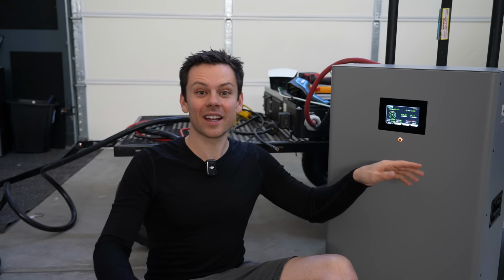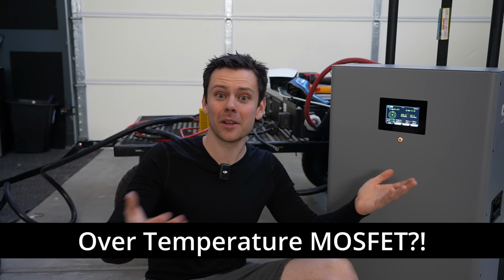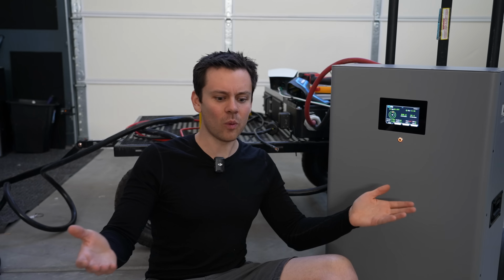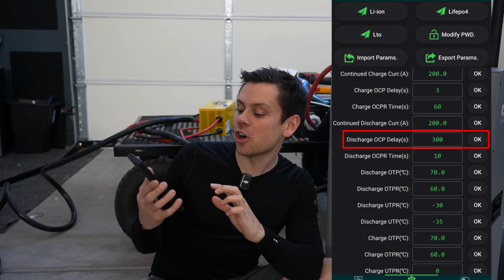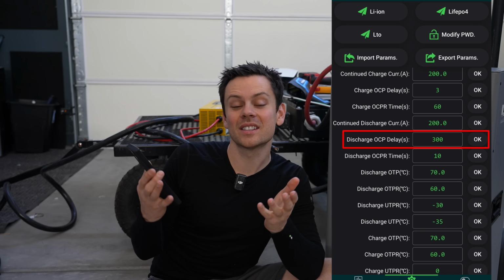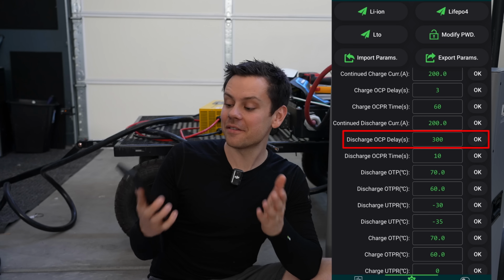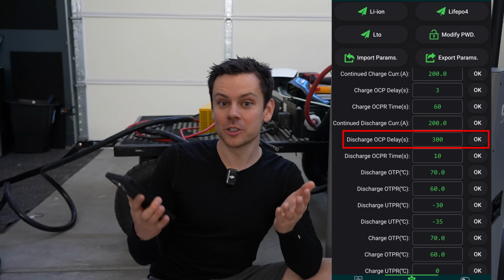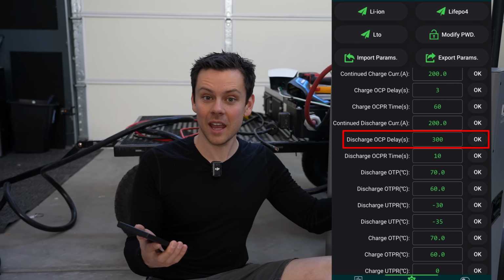The alarm said that I got an over temperature protection for the MOSFETs. And I thought, hey, why is the overcurrent protection not working? It was because the discharge overcurrent protection delay was set to 300 seconds. And I found this issue in the 12 volt model, so it's also present in all the 48 volt models.